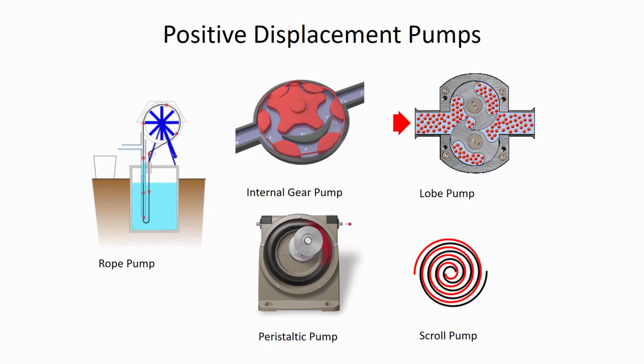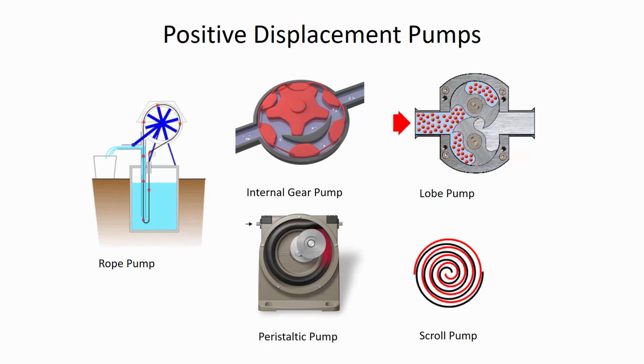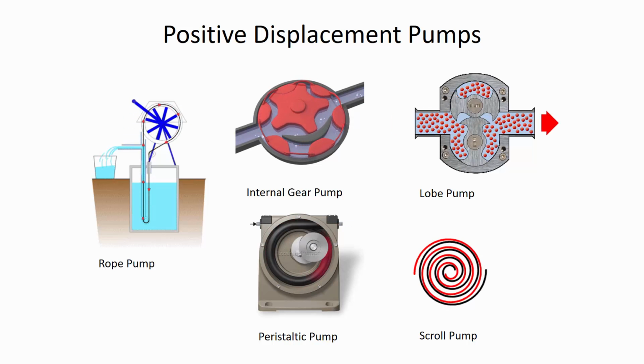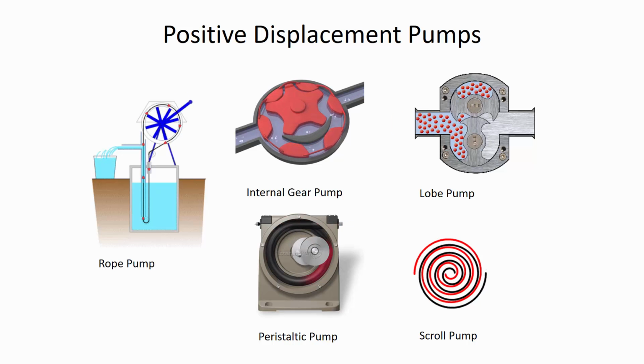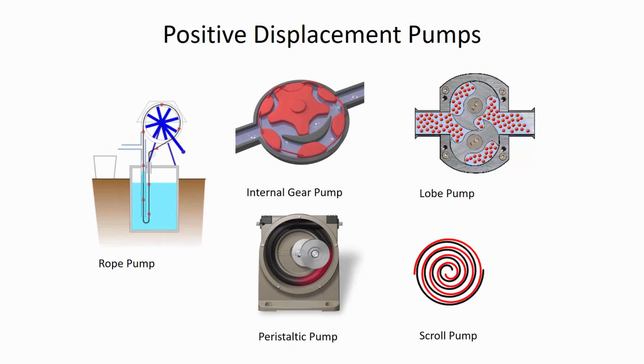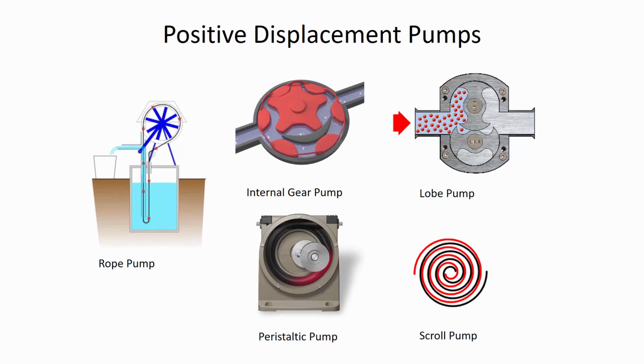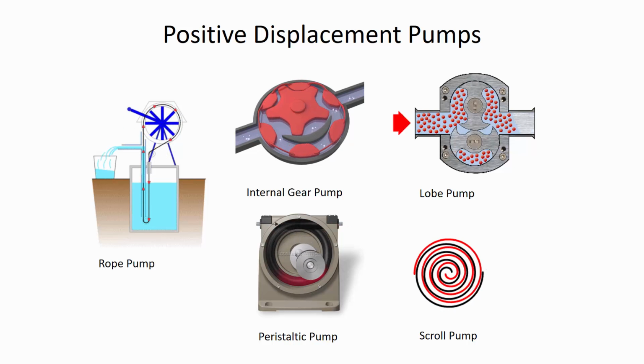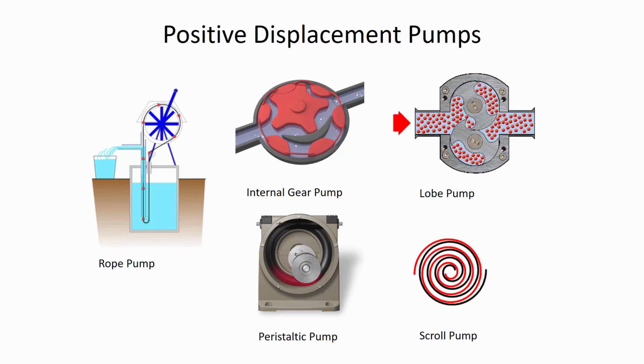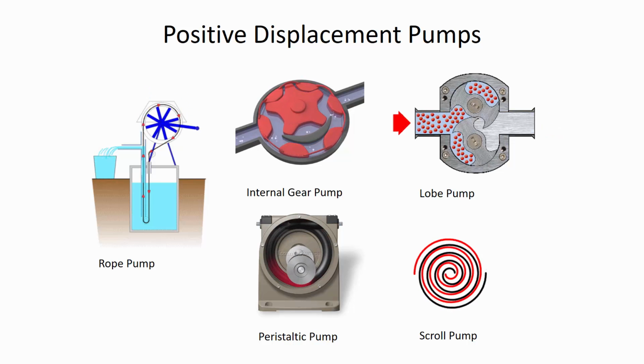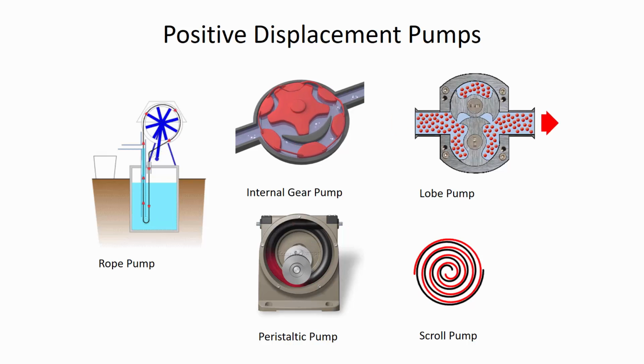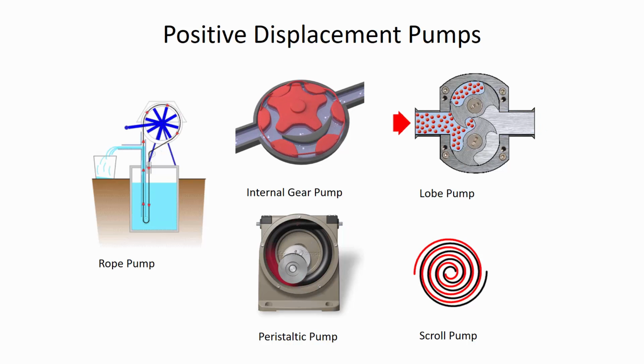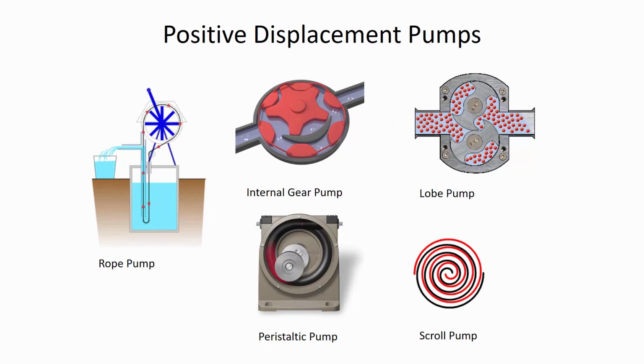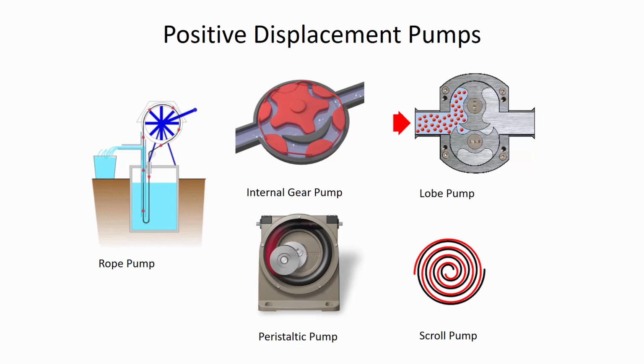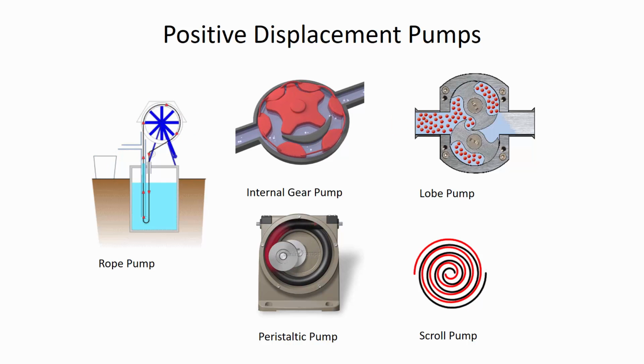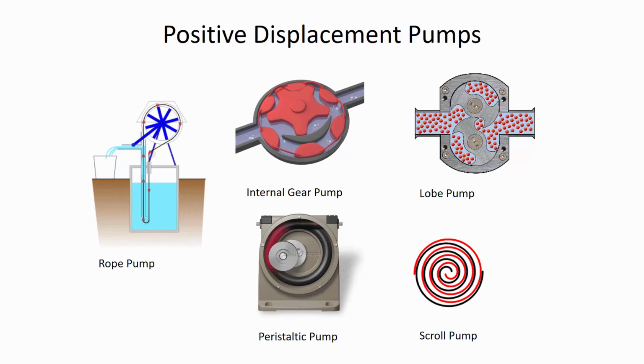The reason why I've used these before is in environmental labs, what you'll often have is flexible plastic tubing. Let's say that you want to pump water from a container of some chemical into a reactor where you want some chemical reaction to happen, and you want a very, very slow but fixed flow rate to go into that chemical reaction. The peristaltic pump is basically a wheel that's pressing against the tubing, and with each rotation, it's forcing a certain amount of water to go through the tubing.